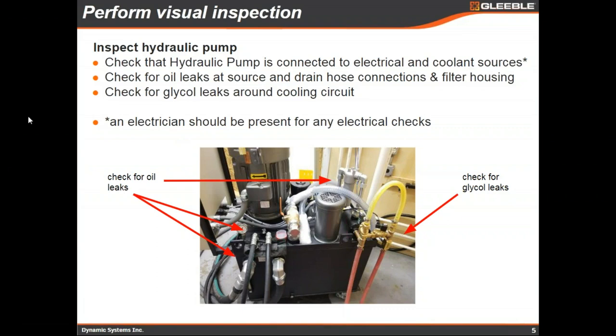For the hydraulic pump visual inspection, the first thing to check is that it's still connected to the electrical power and the cooling circuit. You can see in the picture on the bottom right there should be a few hoses in that cooling loop. Power should be coming in from the top of the NEMA box. It's best to have an electrician present if you're going to do any electrical checks inside the NEMA box.